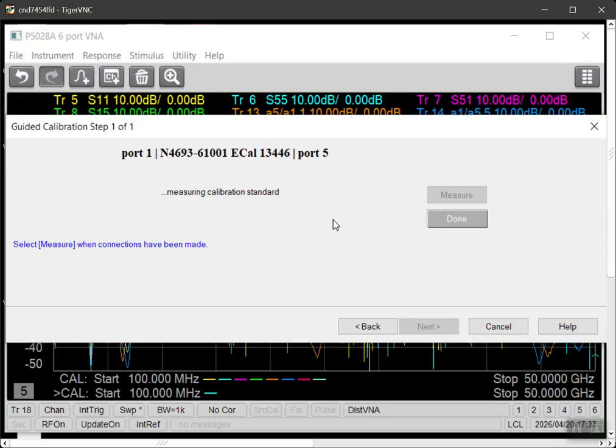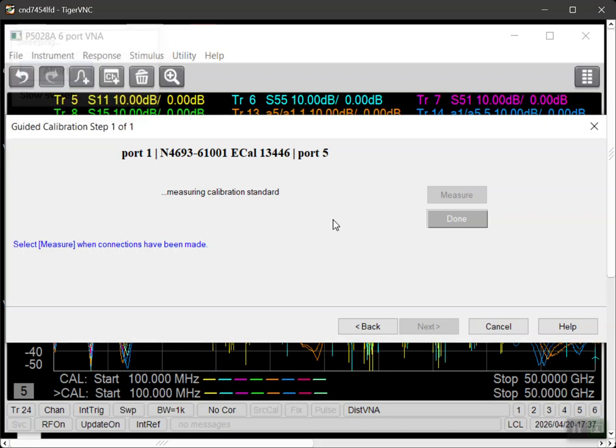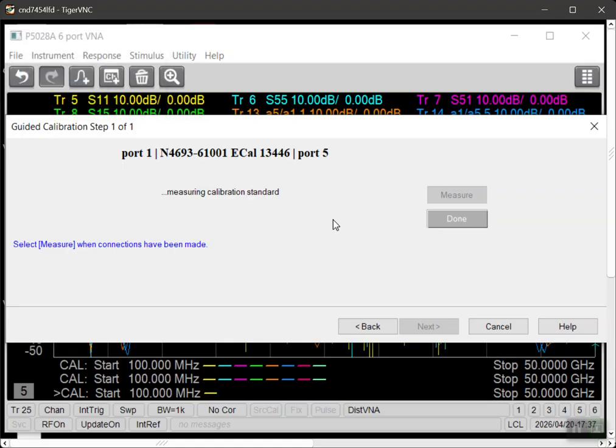And I could have just put S51 in memory. Instead, I've just made 2 channels. So after the cal, I'll put 1 channel on hold, and then I'll copy it to the second channel, and then I will move the cable, and you can see the drift on the second channel, and then we'll apply the auto correction and see how it corrects the measurement.